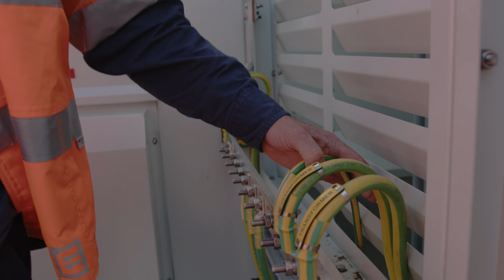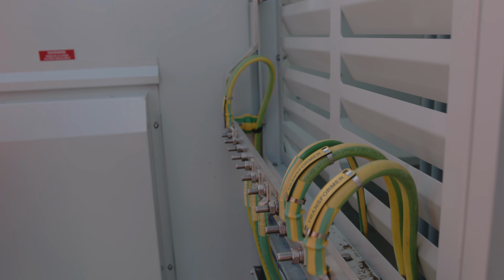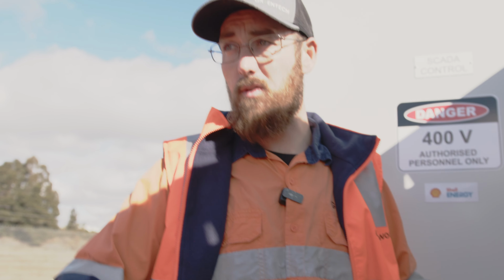For the flashing. So because we're on a HV site, any metal component that can be removed at any time needs to also be earthed. So this is earthed with sufficient length that if you were to take that flashing off while the system's energized for any reason, not that you should, that cable can still be connected to that flashing, protecting you. Yeah, right.